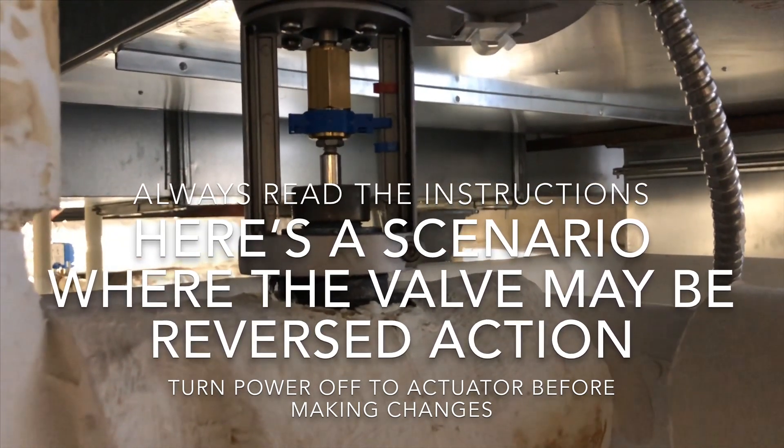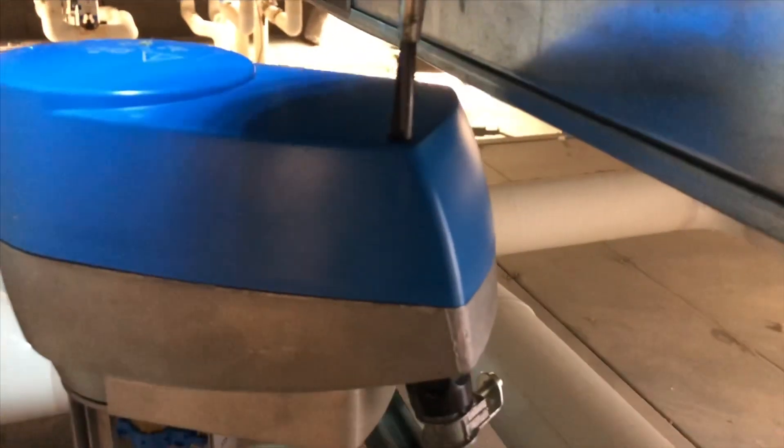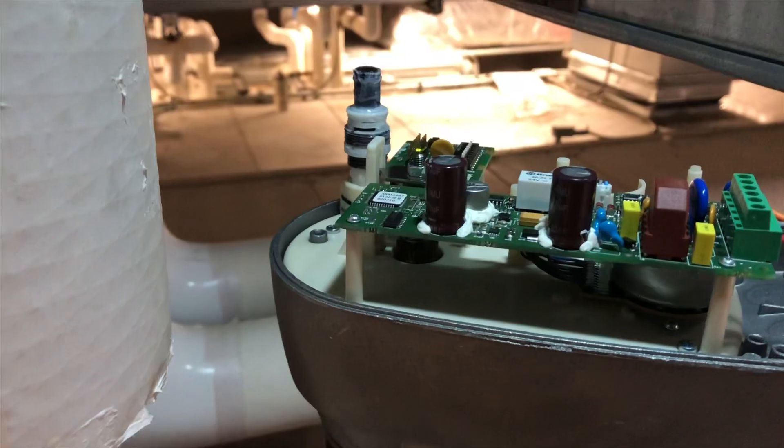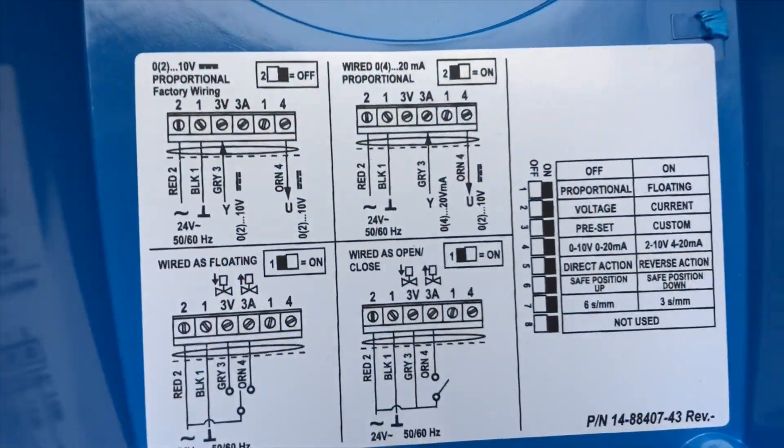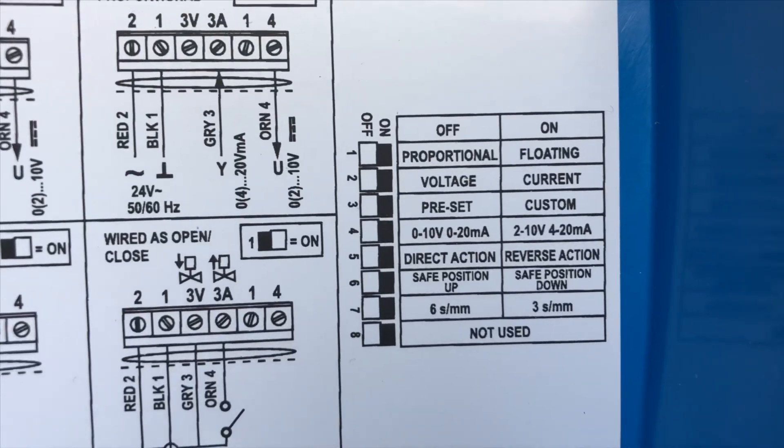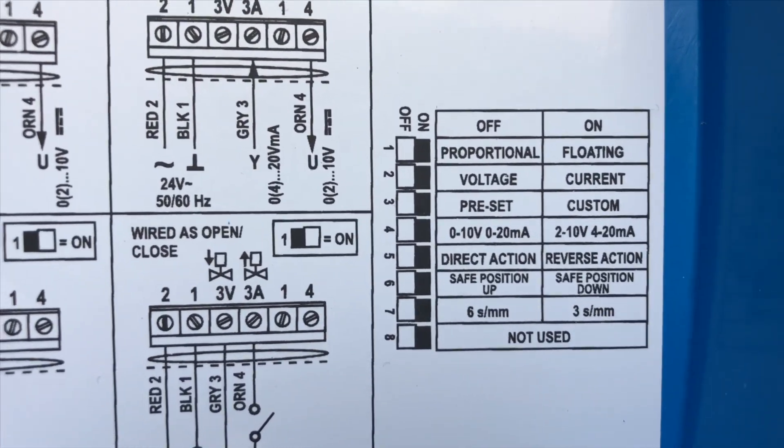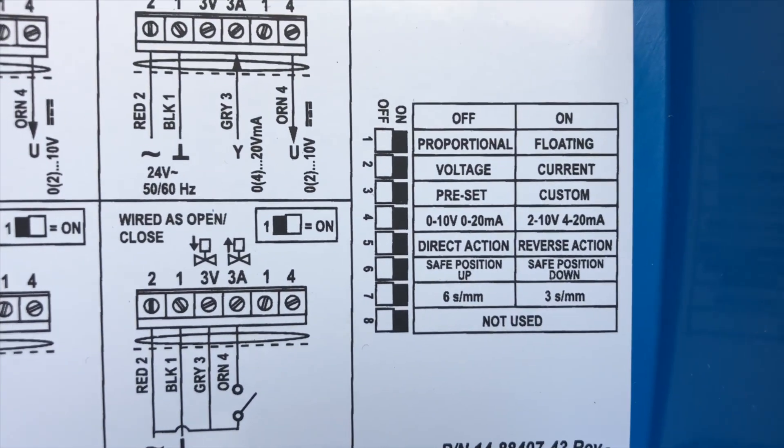We'll take the cover off the top and go from there. We have to gain access to our top of our actuator so we can take these screws out. We'll take our cover off. We got the cover taken off of our actuator. We need to reverse our dip switch here where it says direct action or reverse action.